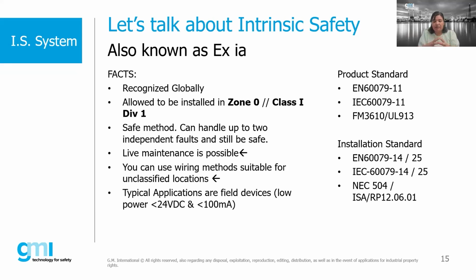Two main things that for me are more critical and important about intrinsic safety is that intrinsic safety will allow you to do live maintenance when energized and in the hazardous areas. And here I want to clarify that live maintenance doesn't mean I'm going to go there and troubleshoot my field device. Live maintenance is I can disconnect that field device and replace it. So I can disconnect intrinsically safe circuits. I can open the enclosure where I have intrinsically safe circuits in the hazardous area while energized, because the system doesn't allow for that energy, that ignition source, to exist.